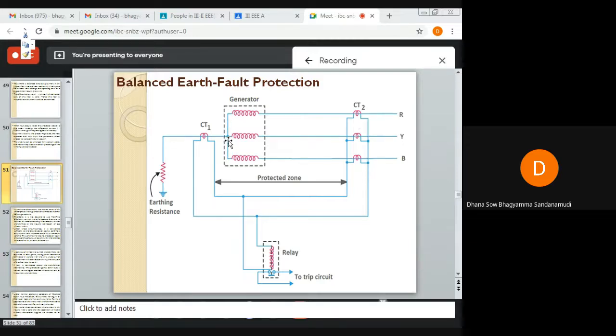The star point is nothing but the neutral point. On the neutral point of this generator winding to the earth, there is a single CT, and the secondary of this CT is connected to the secondaries of these three CTs by pilot wires. The zone between these three CTs and this single CT is the protected zone. Across the secondaries of this CT and these three CTs, there is a relay connected here, and of course the moving contact of this relay and the fixed contacts are shown here. You can see the relay and the trip circuit shown here.